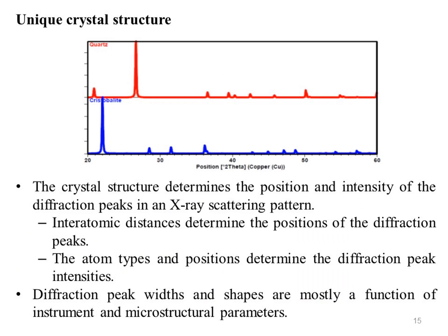The crystal structure describes the atomic arrangement of a material. The crystal structure determines the position and intensity of the diffraction peaks in an X-ray scattering pattern. Inter-atomic distances determine the position of the diffraction peaks. The atom types and positions determine the diffraction peak intensities. The diffraction peak width and shape are mostly a function of instrument and microstructural parameters. In case of quartz you will get a specific diffractogram pattern, and in case of cristobalite you get a different diffractogram.